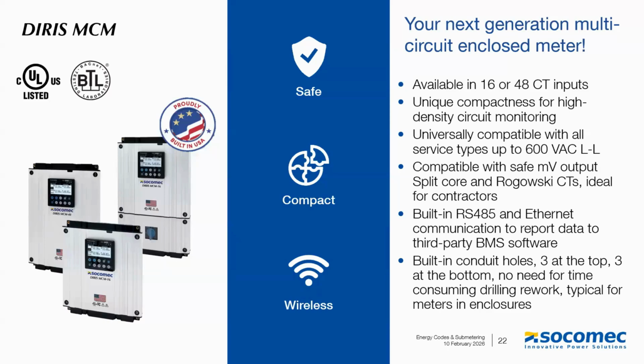So with the DIRIS MCM 48, for example, you can monitor up to 16 three-phase loads, 16 three-phase breakers in a single enclosure. So you're really saving a lot of time on the installation cost, on the installation time, because you have a single voltage reference and you actually have two separate voltage inputs.